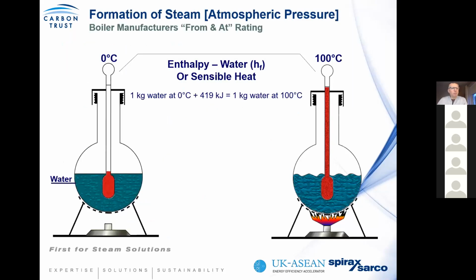So your boiler is designed from what's known as a from-and-at rating. And what that means is that it's designed to generate so many tons of steam within an hour. So if your boiler is designed for, say, 10,000 kgs an hour or 10 ton, it's designed to generate 10 ton of steam at atmospheric conditions.